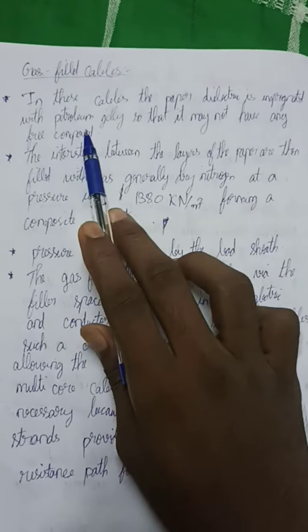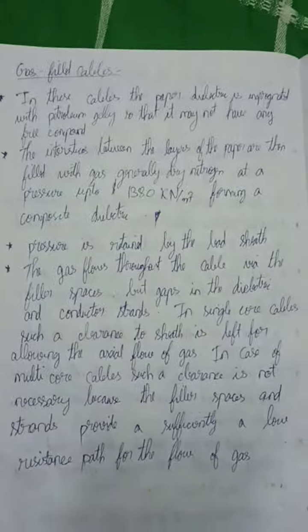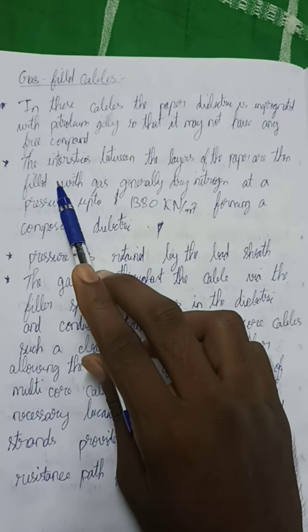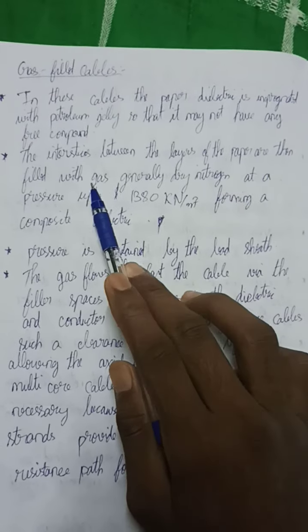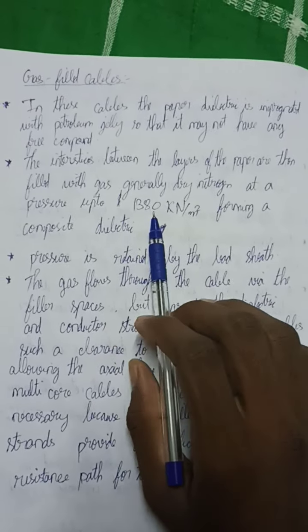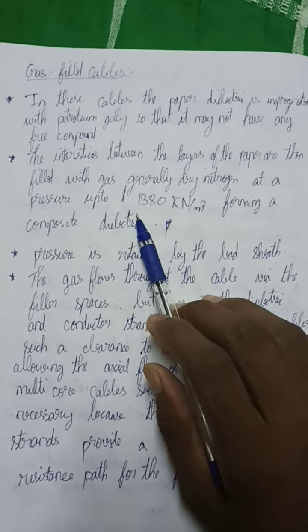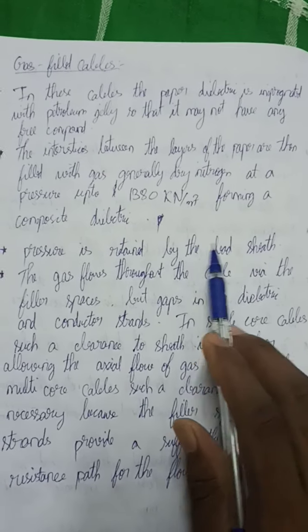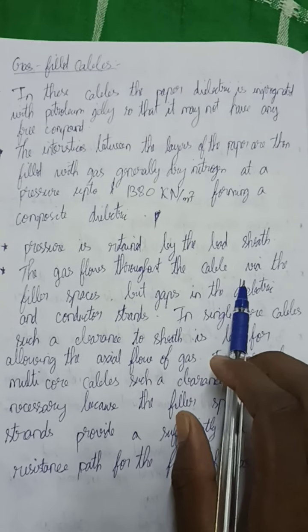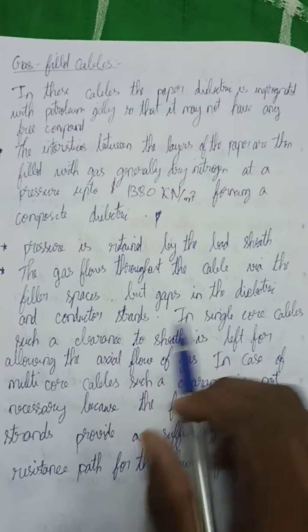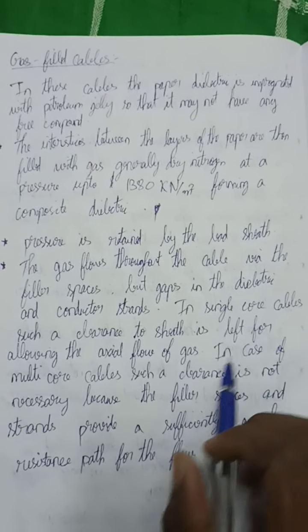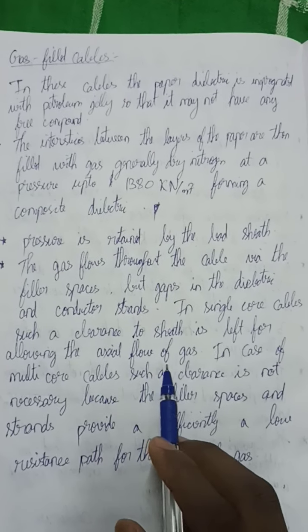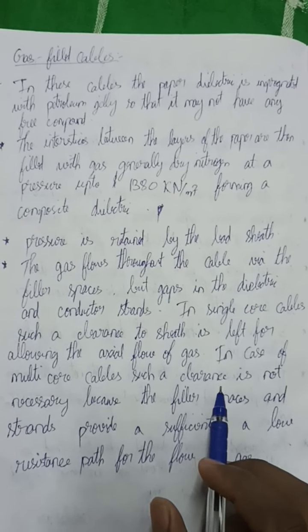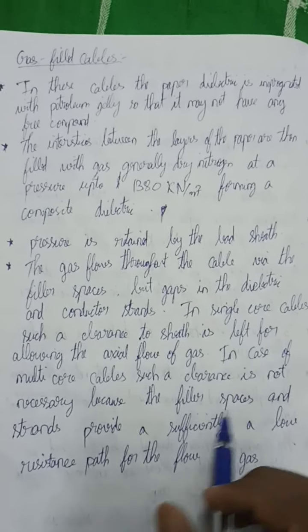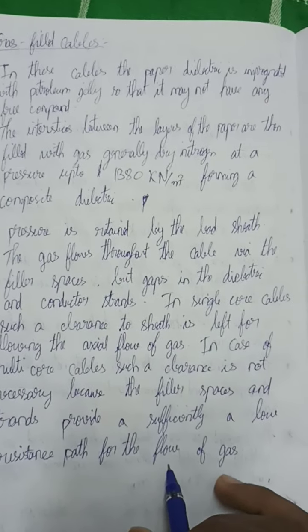Now the gas filled cables. In these cables, the paper dielectric is impregnated with petroleum jelly so that it may not have any free compound. Then the interstices between the layers of the paper are filled with gas, generally dry nitrogen, at a pressure up to 1380 kN/m², forming a composite dielectric. The pressure is retained by the lead sheath. The gas flows throughout the cable via the filler spaces, gaps in the dielectric and conductor strands. In single core cables, a clearance to the sheath is left for allowing the axial flow of gas. In multi-core cables, such a clearance is not necessary because the filler spaces and the strands provide a sufficiently low resistance path for the flow of gas.